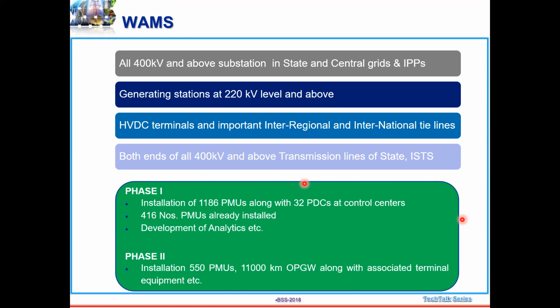Then there will be 416 PMUs that are already installed at various locations. We will be having them in Madakathara, Kayamkulam, and Idukki. And development of analytics is already there. It's already developed and it's under testing now. The analytics for PMUs is being developed by IIT Mumbai, and it's already installed in SLDCs and RLDCs, and it's under testing now. In Phase 2, we will have another 550 PMUs installed with the OPGW installation. All the communication will be through OPGW.